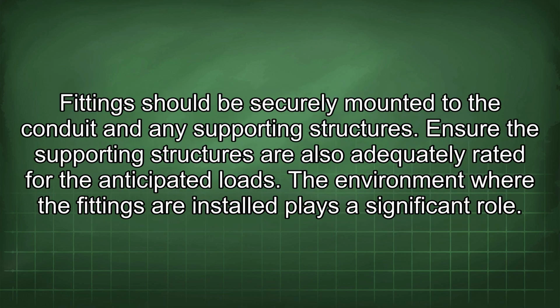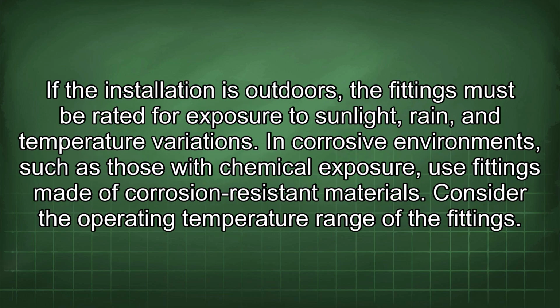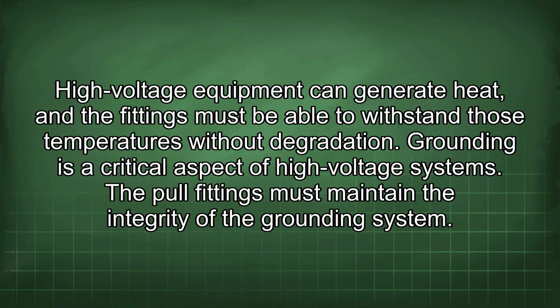Fittings should be securely mounted to the conduit and any supporting structures. Ensure the supporting structures are also adequately rated for the anticipated loads. The environment where the fittings are installed plays a significant role. If the installation is outdoors, the fittings must be rated for exposure to sunlight, rain, and temperature variations. In corrosive environments, such as those with chemical exposure, use fittings made of corrosion-resistant materials. Consider the operating temperature range of the fittings. High-voltage equipment can generate heat, and the fittings must be able to withstand those temperatures without degradation.